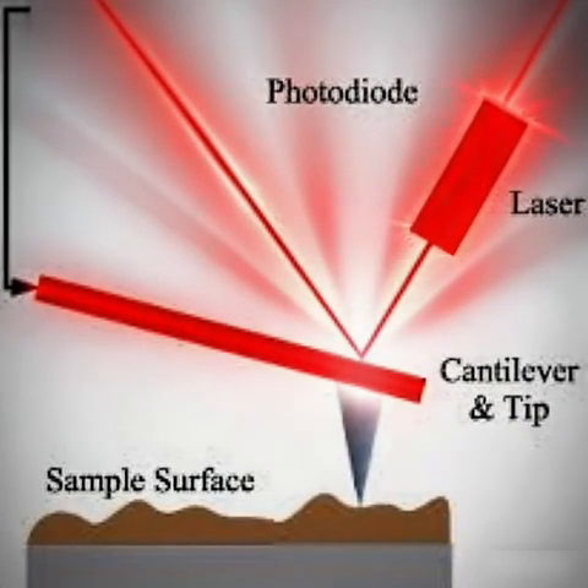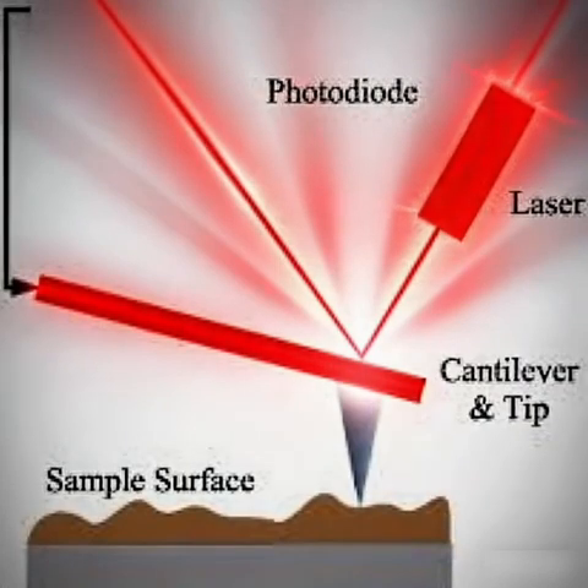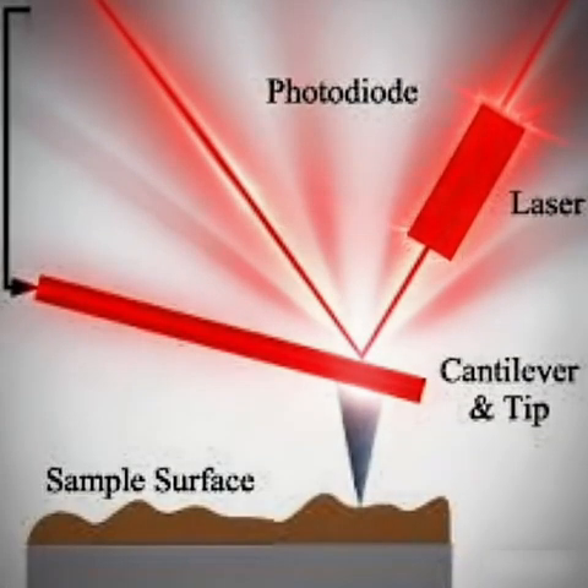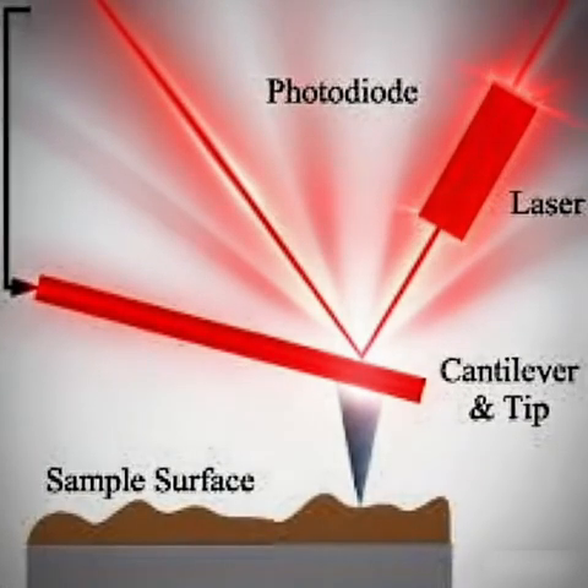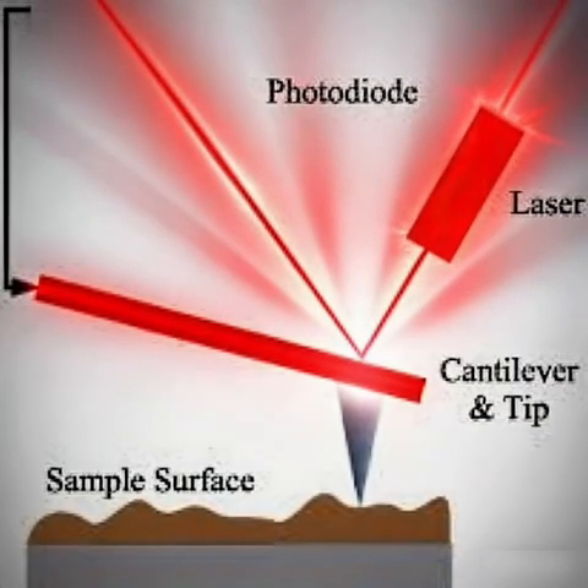That's an excellent point. Yes, that happens. Often, EFM might highlight an area with unusual charge buildup, suggesting a potential defect. But it doesn't necessarily tell you if that defect is critical, if it will cause a breakdown soon. So you can then use nano-TDDB precisely on that suspicious spot to directly assess its electrical strength and predict its lifetime. And yeah, sometimes you might find a strong EFM signal that doesn't lead to an immediate breakdown with nano-TDDB. Maybe it indicates a less severe issue, or maybe it's just a surface charge not related to a deep flaw. Or the other way around, maybe a spot looks okay with EFM but fails quickly under nano-TDDB stress. Reconciling those data points, that's really part of the art of failure analysis. It guides engineers to zero in on the most vulnerable, most likely to fail areas at the nanoscale.